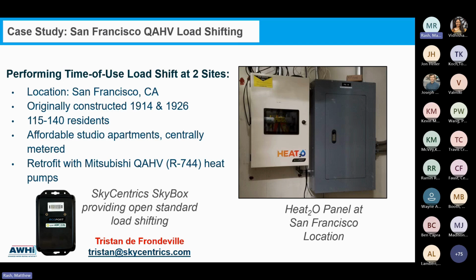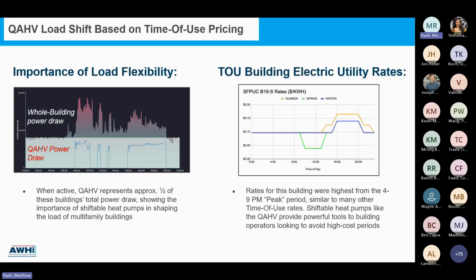It'll give you that full expansive point list for each of these options, but it's pretty extensive across the board in terms of what's in that BACnet integration with this solution. You also have over-the-air update options with that as well. So again, that's an added option, but that's really what unlocks the full capabilities of those two solutions. With the core, you basically have to have the QAHV control panel. That's what manages the lead, lag, and staging of the components.